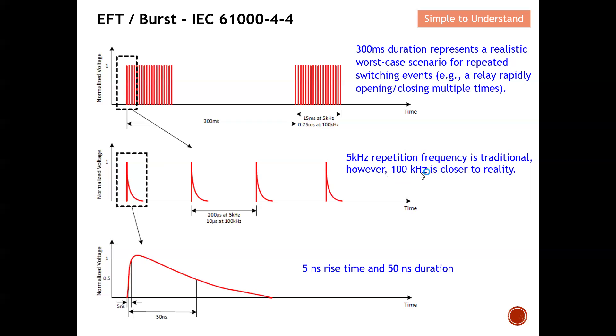If we zoom into a single pulse, you can see that the 5-nanosecond rise time and a 50-nanosecond pulse duration — at least 50 percent. This is the signal pulse we send to disturb your DUT, and we want to see whether your DUT can still function.